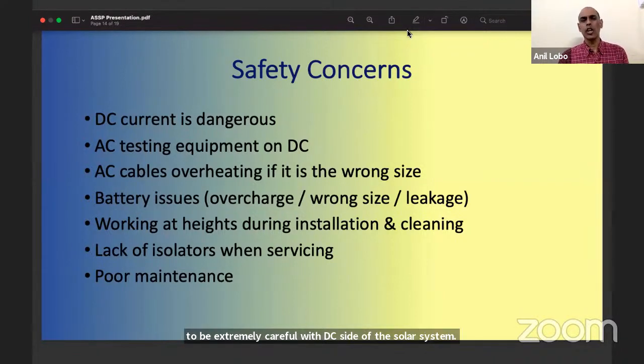The second thing is your AC equipment. You can't use your standard AC testing tools to determine whether it is working or not. Your AC testing equipment does not work on DC. You have to use specialized DC tools which are used by low voltage technicians. But now the low voltage technicians work on 12 volts, at the most 24 volts, and in very rare cases they work up to say 48 volts DC. But here you're going to 300 and 400 volts. So you have to be very careful what type of testing equipment you're using on the DC side. The third problem is DC cables overheating if they are the wrong size.